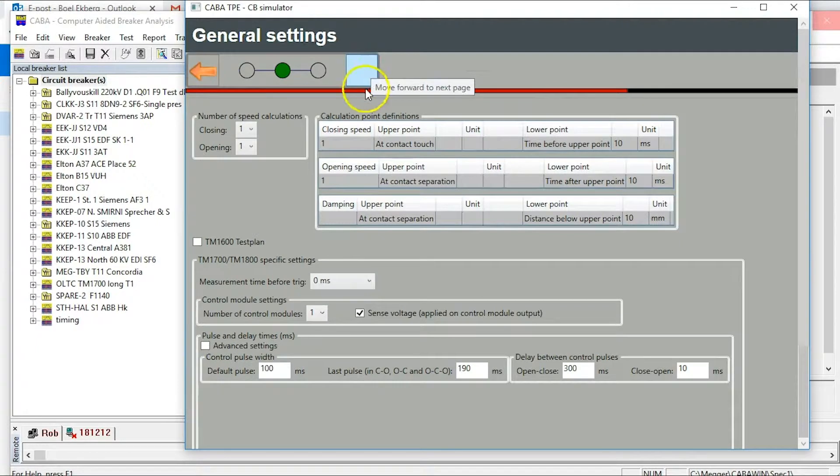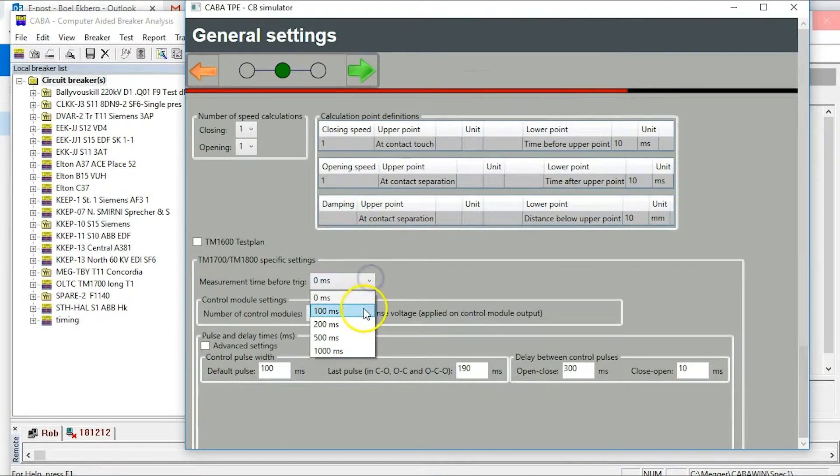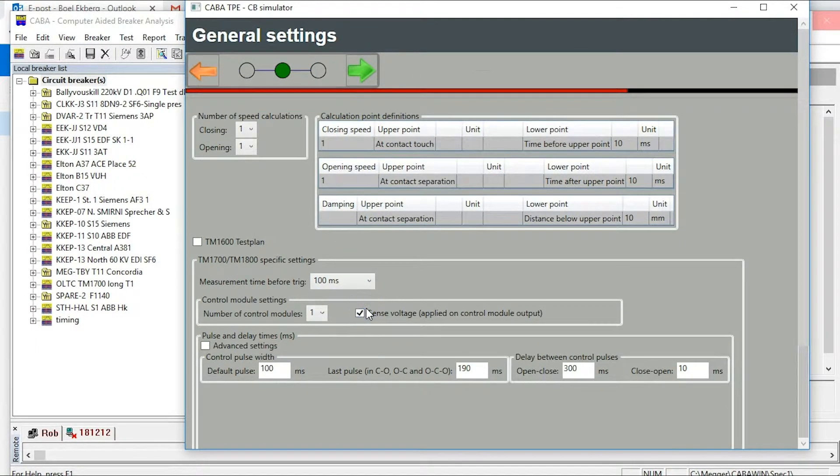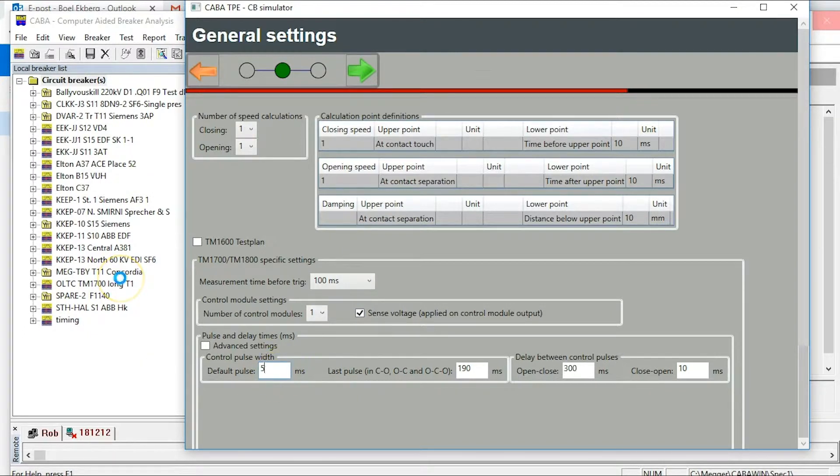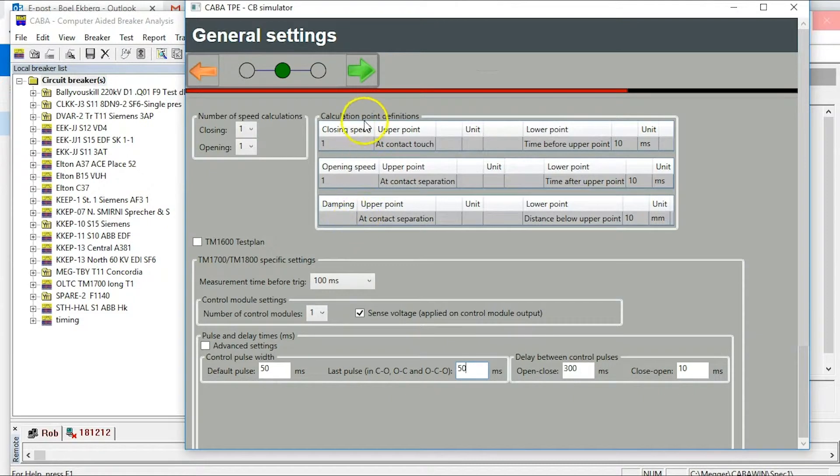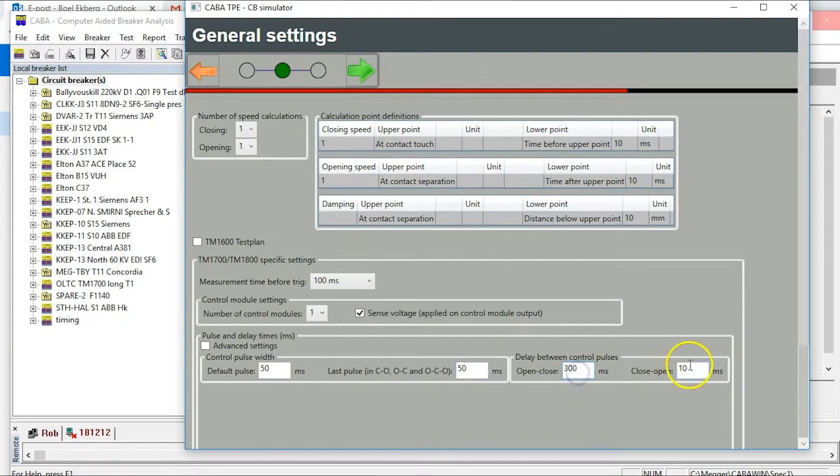Select pre-trig time setting to measure before time zero. Set short time for pulses. 300 milliseconds is IEC demand for this delay.